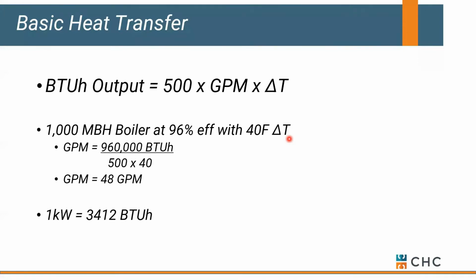We're seeing a lot of electric with decarbonization going on right now. And 1 kW is equal to about 3,400 BTUs an hour. If we apply that to our million BTU boiler, that's about 293 kW. That just means your meter's going to spin a lot if your boiler gets to high fire, or full output on an electric boiler.